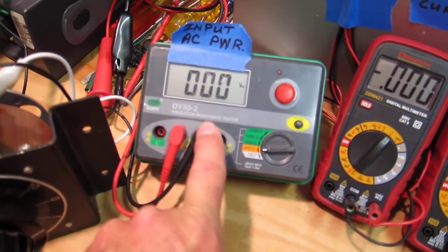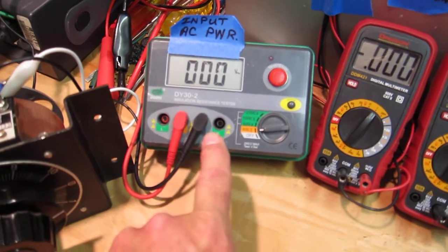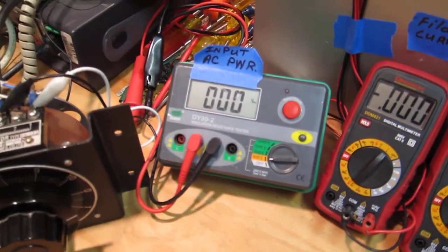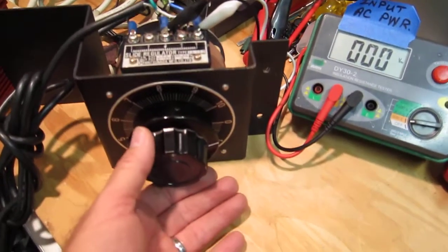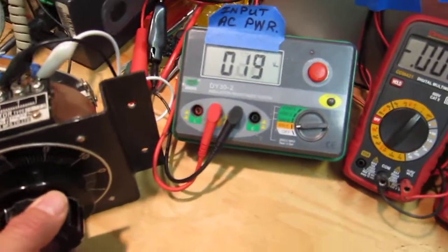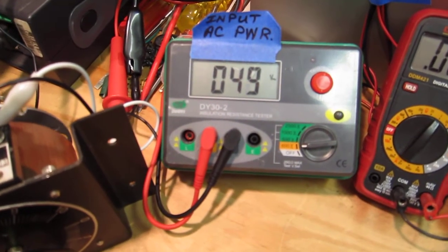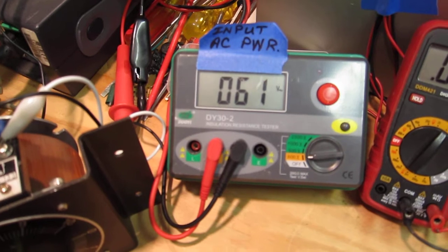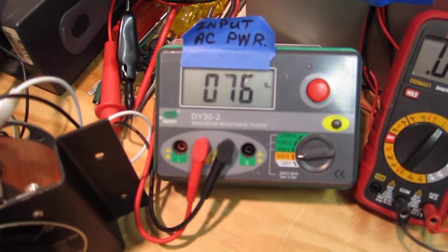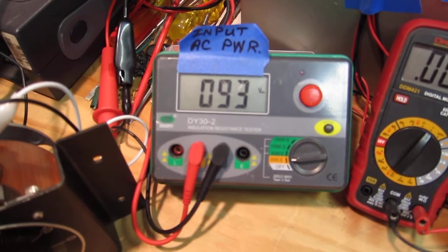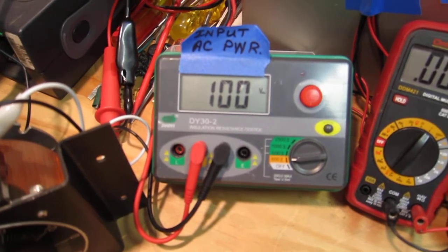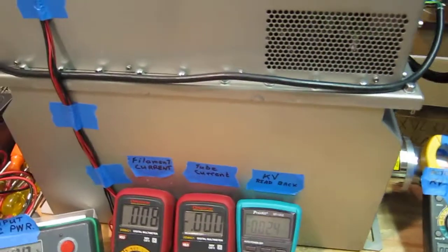Here I can read the AC voltage going in. The XRG-160 is capable of being powered from 90 volts AC up to 240 volts AC. I've got a variac transformer here, and I'm going to turn it up to approximately 100 volts, as if you were operating it in Japan, perhaps, with the AC power they have there. So there I am at 100 volts AC going in, and you can see I've already got the main power switch turned on, so you could hear the cooling fan that's over here blowing air out.